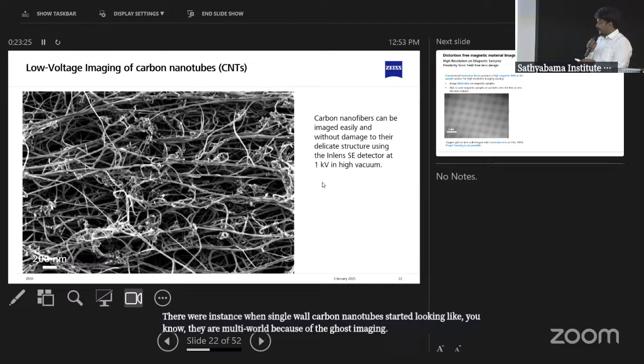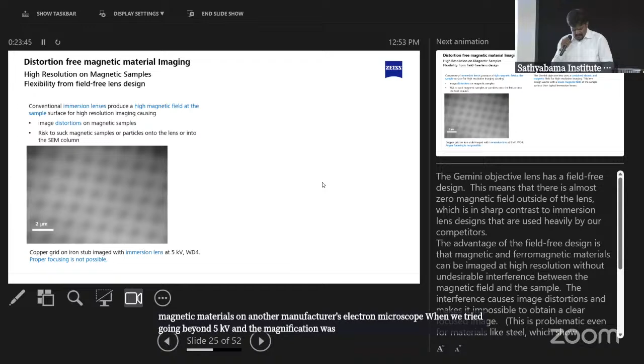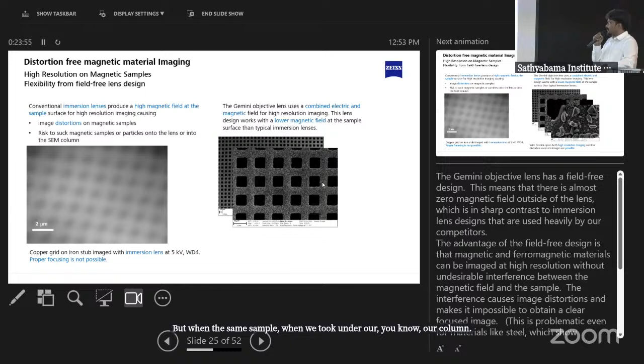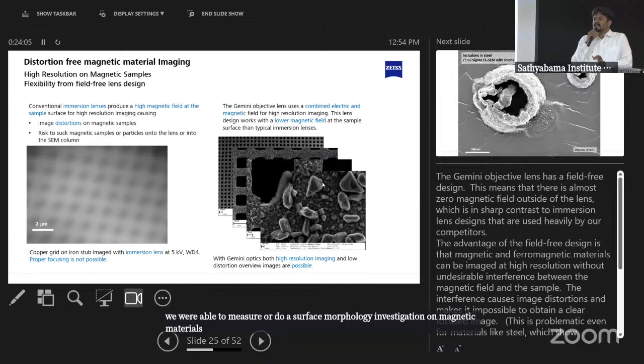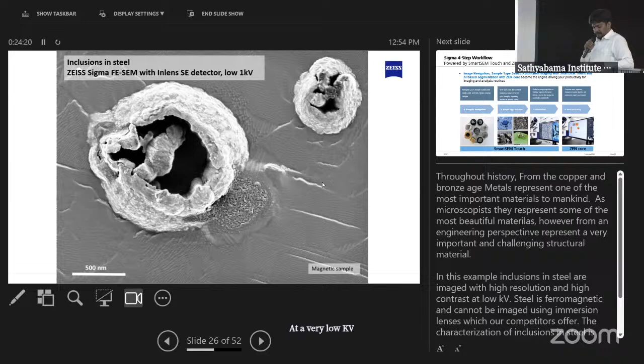And this is an example where I wanted to stress characterizing magnetic materials. We tried doing imaging of magnetic materials on another manufacturer's electron microscope. When we tried going beyond 5 kV, at a magnification somewhere around 5,000 times, it was completely distorted. We were not able to see anything. But when we took the same sample under our column, you can see here the resolution at which we were able to push, and very clearly we were able to do a surface morphology investigation on magnetic materials all the way down to 40 to 50 nanometer dimensions as well. That's where we are able to comfortably do it. And this is again a magnetic sample where it had some inclusions. We were very clearly able to capture it at a very low kV imaging as well.